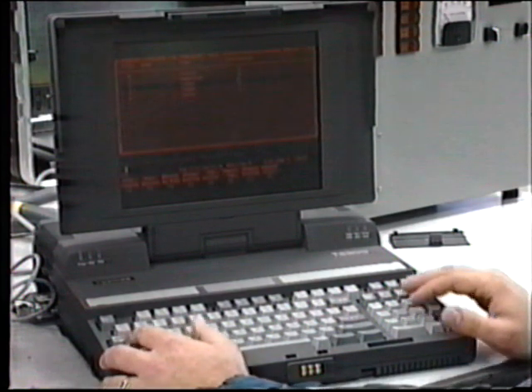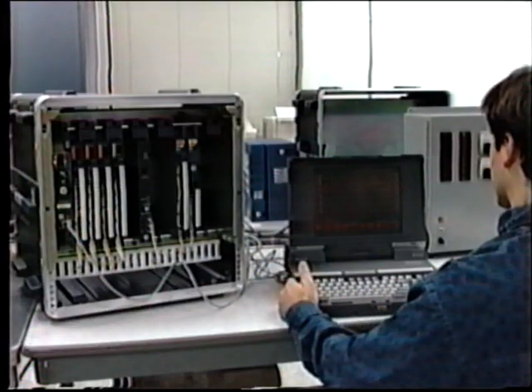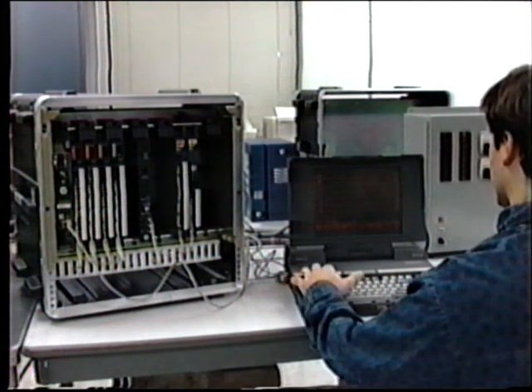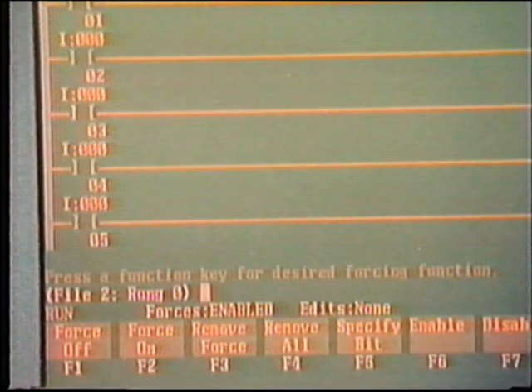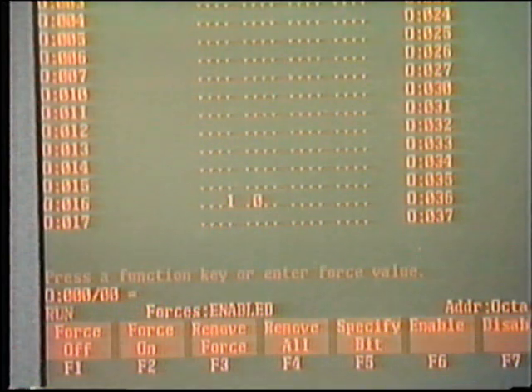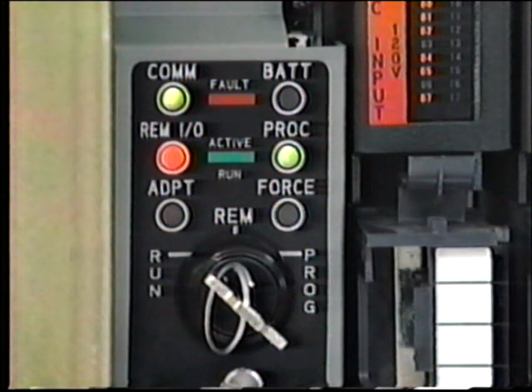Many programmers are helpful in allowing you to access the control circuits online. You can examine on the programmer's screen each rung of the ladder and observe which contacts are open or closed and the state of inputs and outputs. You can also force close or open selected input and output contacts in order to check the operation. Usually, forced operation of input contacts causes the outputs to be isolated so as to prevent inadvertent operation. Forced outputs can bypass safety permissive contacts, causing machine action. Therefore, use care when forcing outputs.